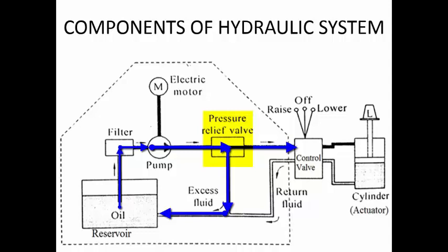Now the question is, why do we have a reservoir? The reservoir will collect all the fluid that is coming from the system. We cannot waste the oil, so oil will be stored in the reservoir. Apart from that, the reservoir will ensure that there is some amount of oil always present on the suction side, so that no gas or air is sucked into the hydraulic system. You have different piping elements which connect the different parts of the hydraulic system, and all the oil has to be brought back into the reservoir.